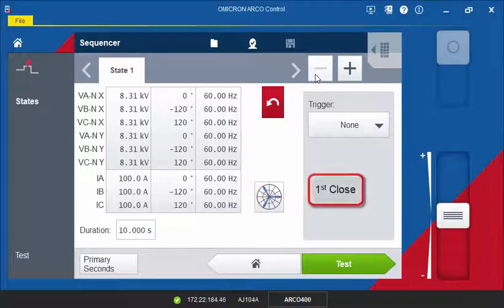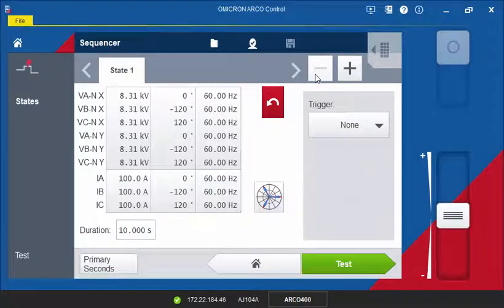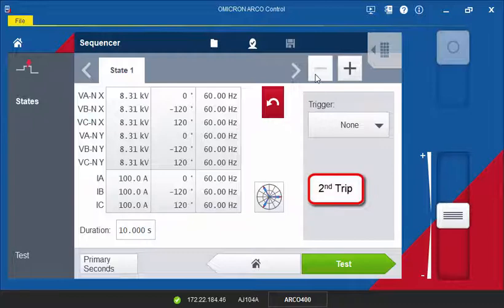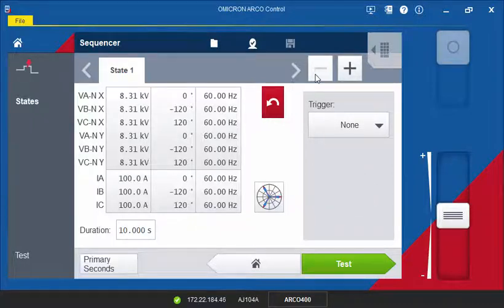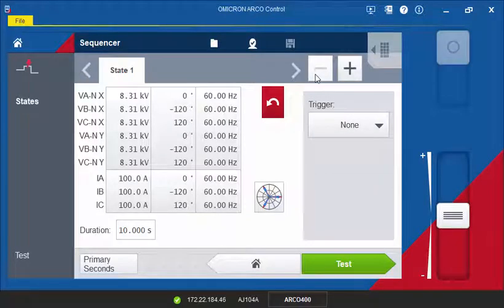Afterwards, we will add a state where we wait for the first close and followed by another fault state where we will expect a second trip. In the last state, we want to verify that the controller does not reclose.